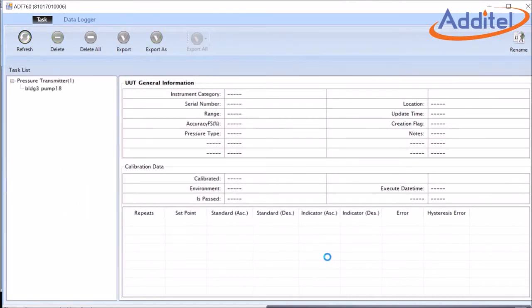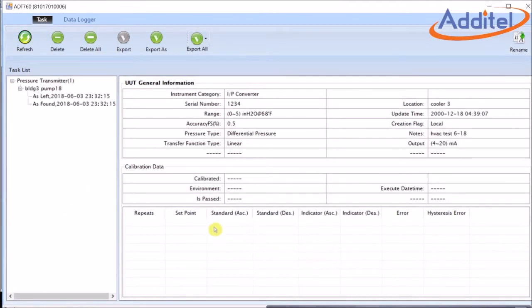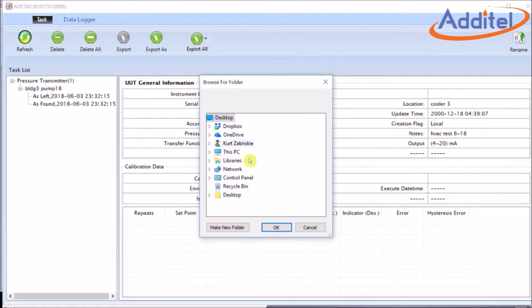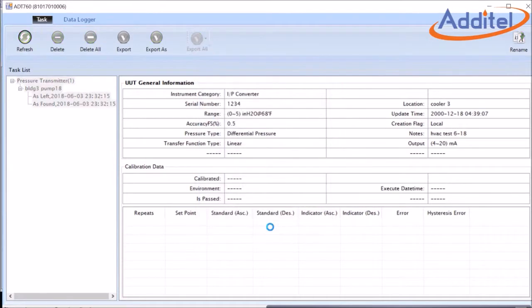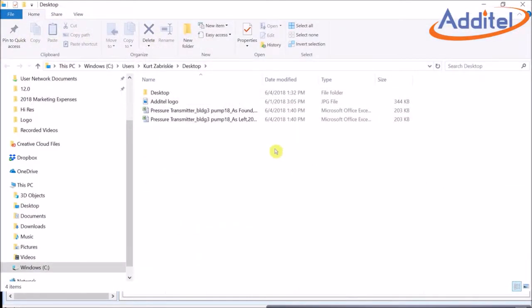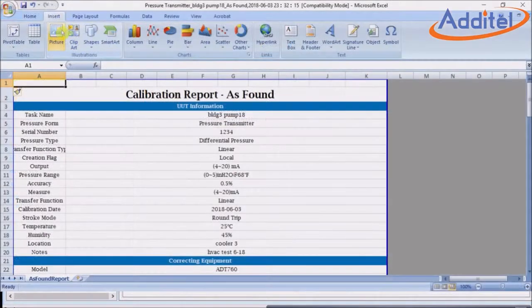From the Query dialog box, we'll want to make sure that the Pressure Transmitter option is selected, and then click OK. From here, we should be presented with a list on the left. You'll note our As Found and As Left data. We will export all the data by clicking the Export All button in the upper right corner, and then export to Excel. I'll choose to have the data sent to my desktop. From there, the desktop will open up, and I'll be able to select the As Found data.